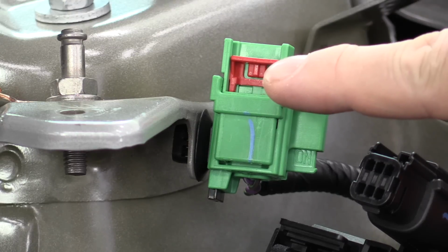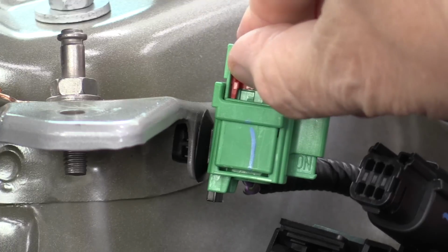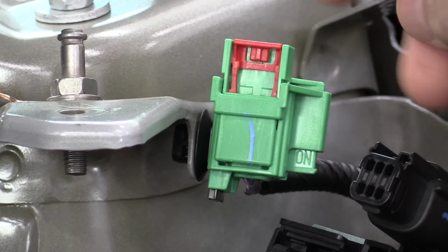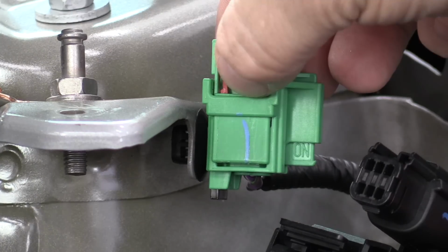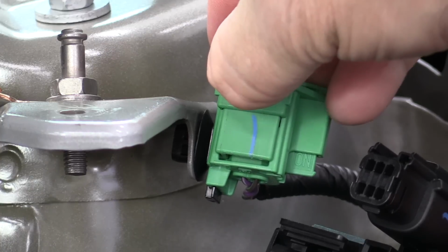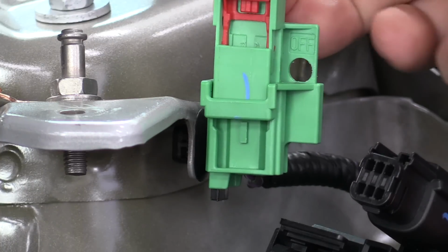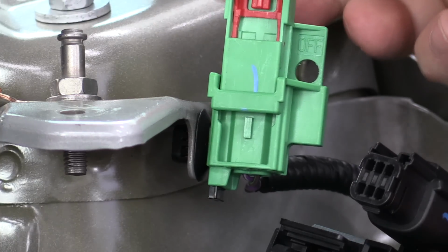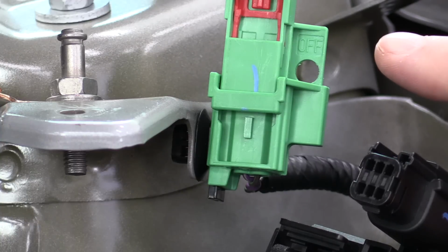But we need to depower and deactivate that system. There's a red connector position assurance clip right there, so I'll lift up on that. Then there's a green tab - push in on it and lift up. Notice now that I've lifted up, we have the word 'off' right there, meaning the low voltage power to the contactors, which allows them to close when commanded, has been removed.